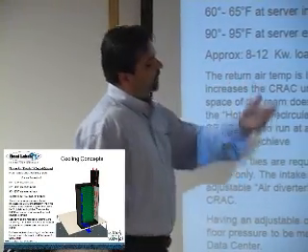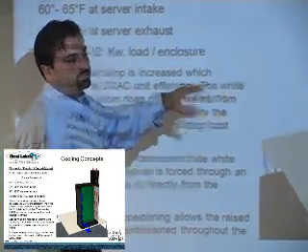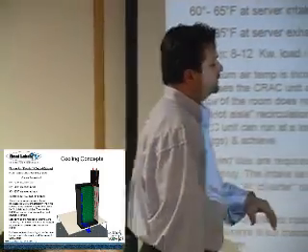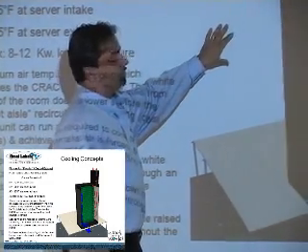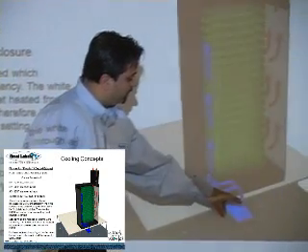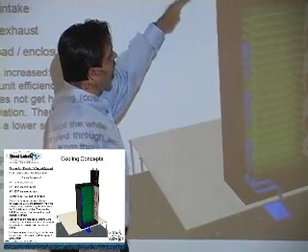But what we're seeing now, when you're able to do this, your chilled air does not have to actually cool the room. This is the simplest cost-effective way to do it, where you can keep your CRAC unit the same or achieve a higher density. You don't actually have to chill the air here. It actually helps you get some pressure from the raised floor, the floor tile. Right now we're using perf tiles, and we're hoping that the chilled air comes all the way up and isn't sucked in through the mesh as well.